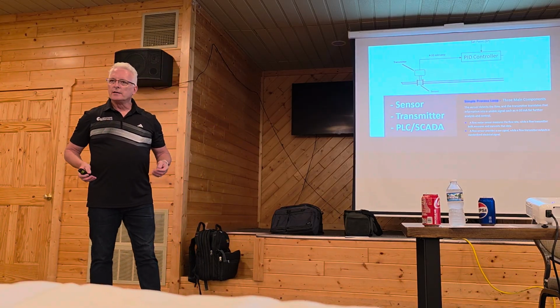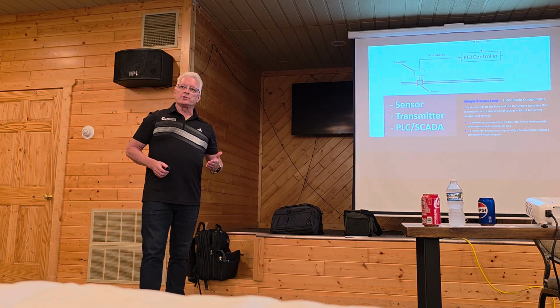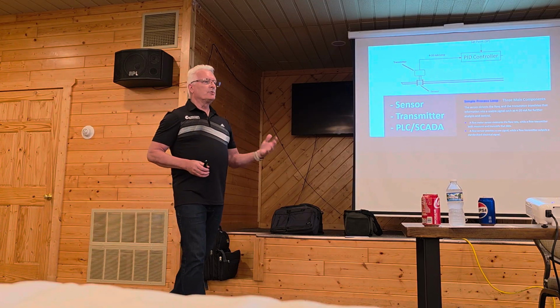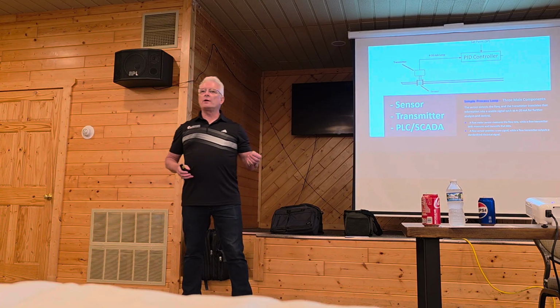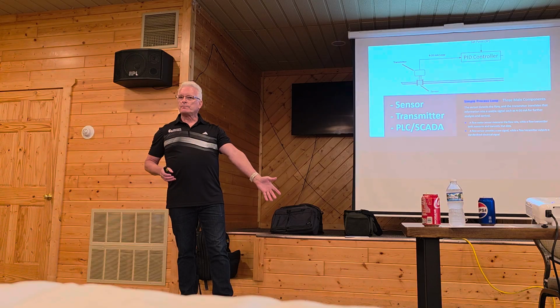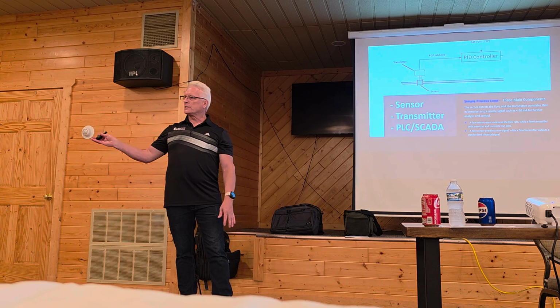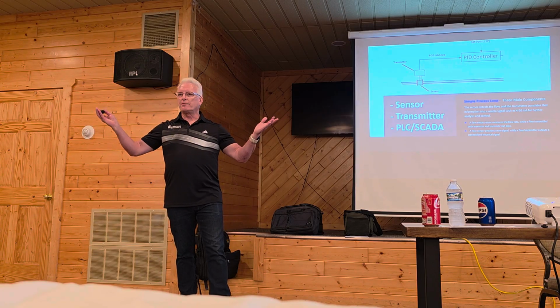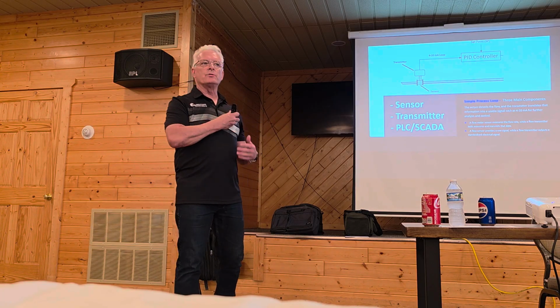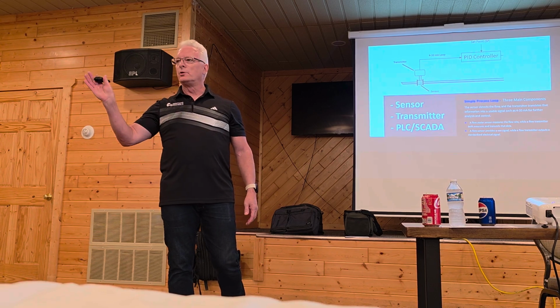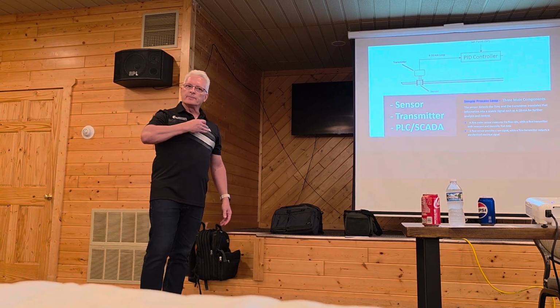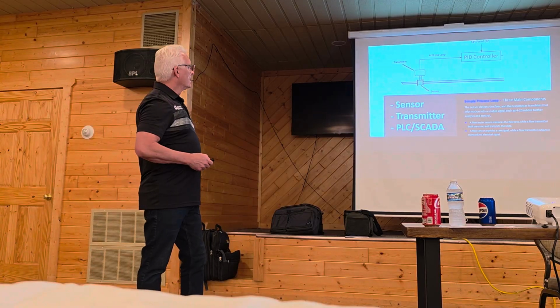Nothing will be right. A lot of people go out and do calibrations, and the only thing required is to do the input part of it. So if you do a calibration on the flow meter, and you just did the input part, but the 4 to 20 is not right, you're only halfway there. You don't know. So we try to do the whole flow, all the way through the whole thing, to make sure it's right.